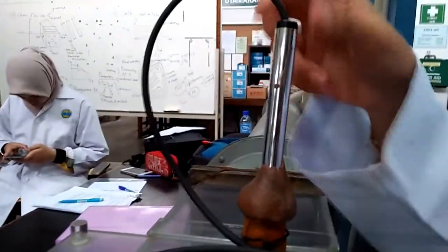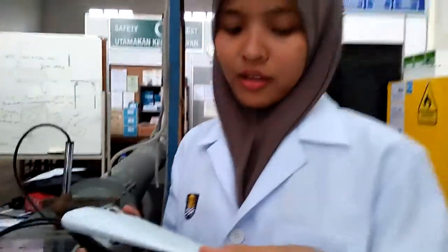HWA is a method of measuring fluid velocity by measuring the heat transfer from a small wire. This probe contains the heat element. The rate at which heat is removed from the sensor is directly related to the velocity of the fluid flowing over the sensor. So by measuring the amount of current required to maintain the sensor at a constant temperature, we can obtain the fluid velocity.